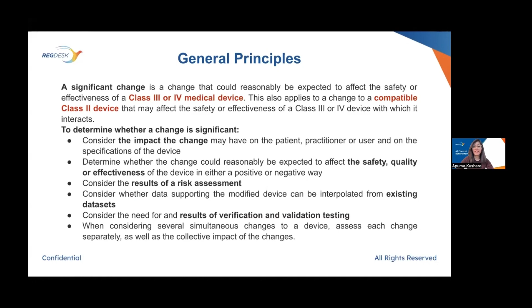So it is important to consider the impact the change may have on the patient, practitioner, or users and on the specifications of the device. Determine whether the change could reasonably be expected to affect the safety, quality, or effectiveness of the device in either a positive or a negative way. It is very important to consider the results of the risk assessment. So we will be going into details about these three parameters in our next segment. It is important to consider whether the data supporting the modified device can be interpolated from the existing data sets. And it is also important to consider the results of verification and validation testing. In a scenario where there are multiple changes to a device, it is important to assess each change separately and also understand the collective impact of the changes.